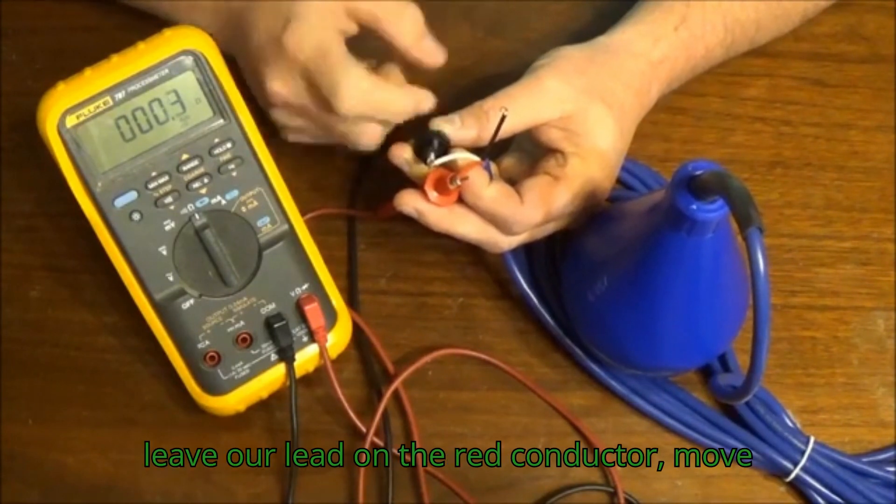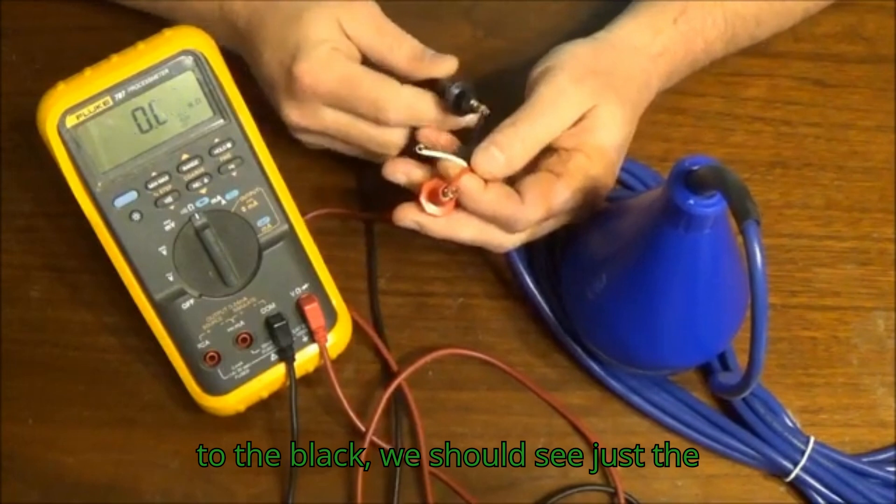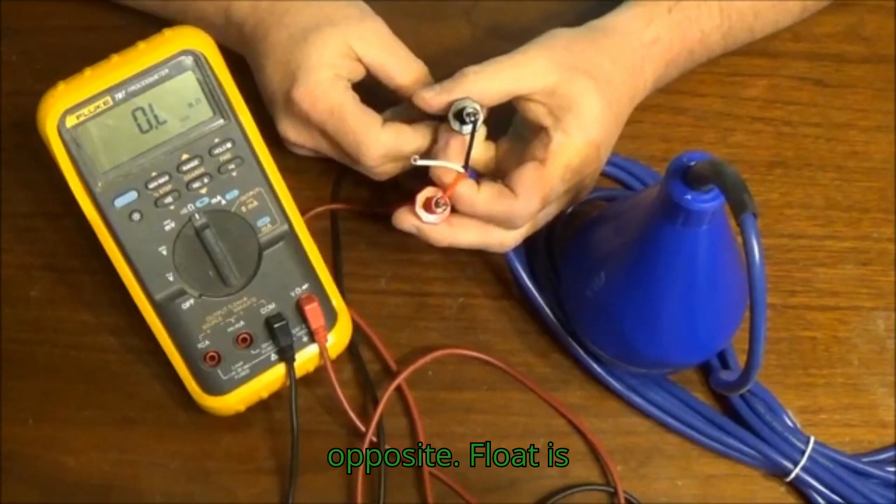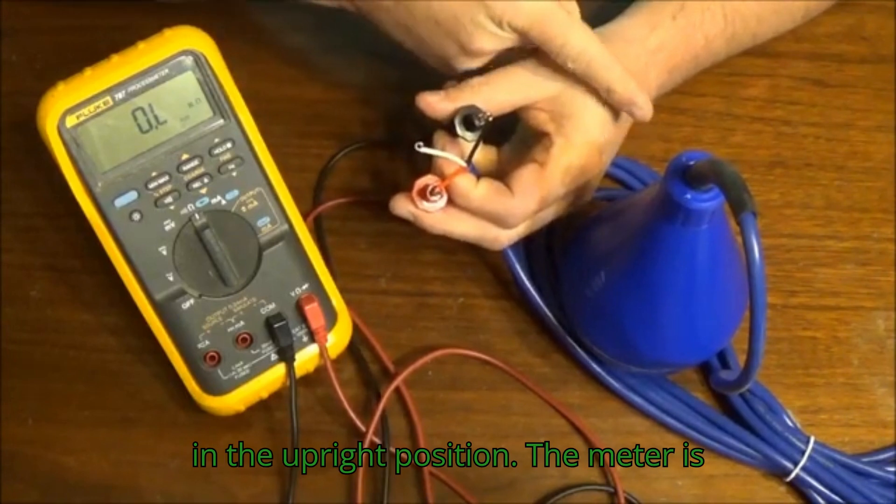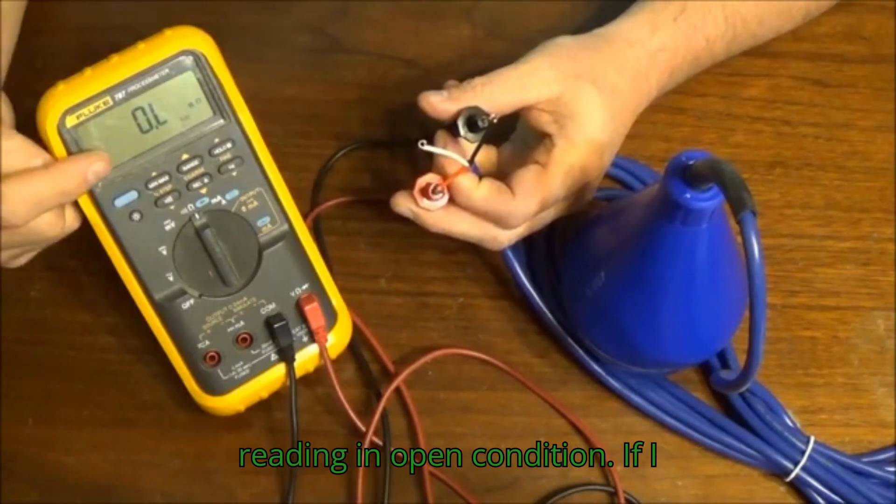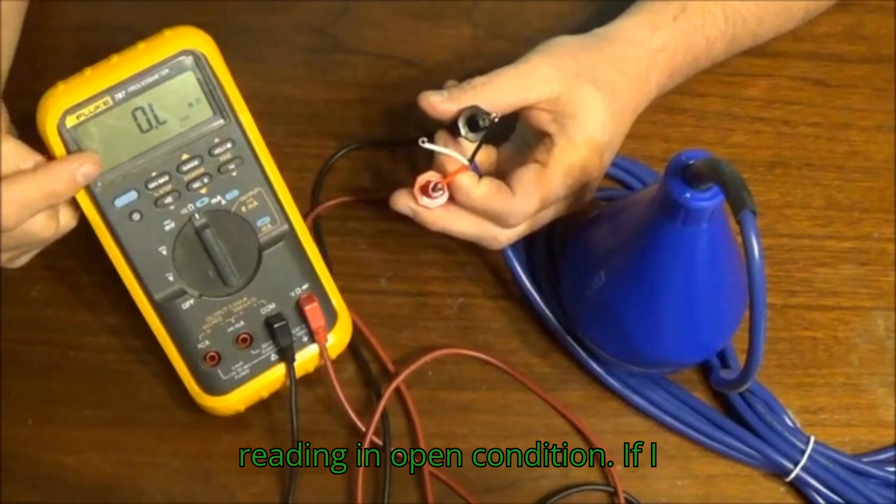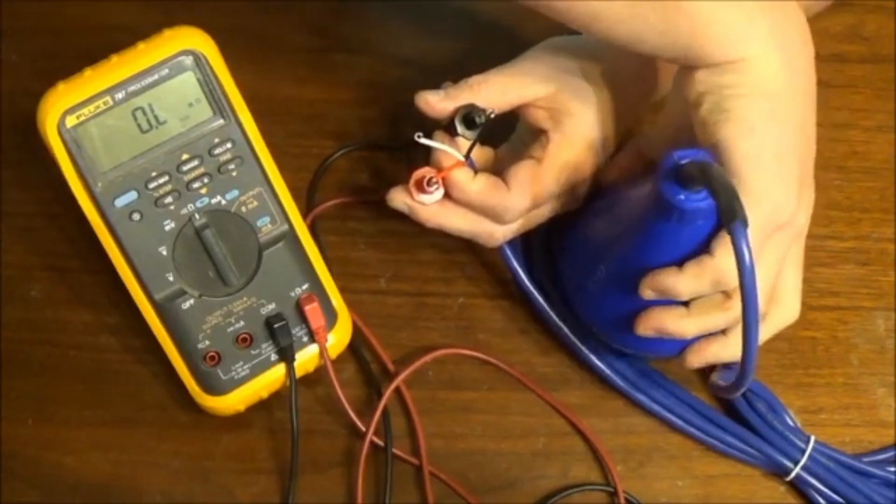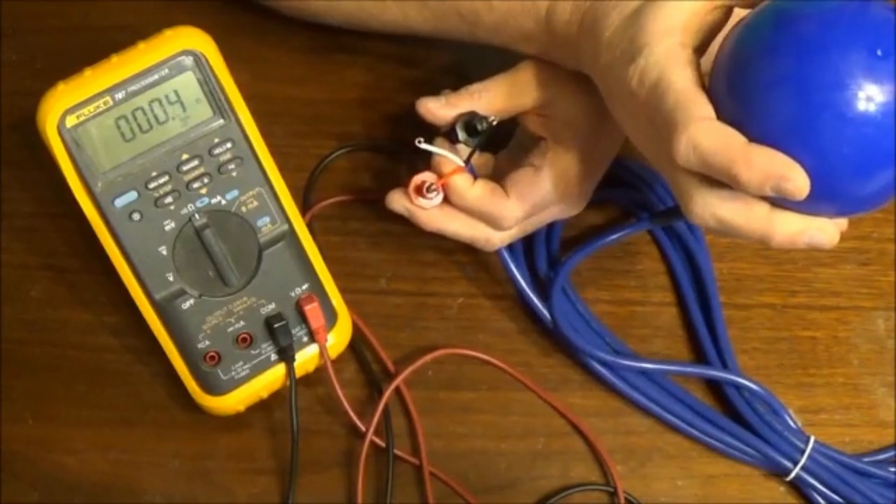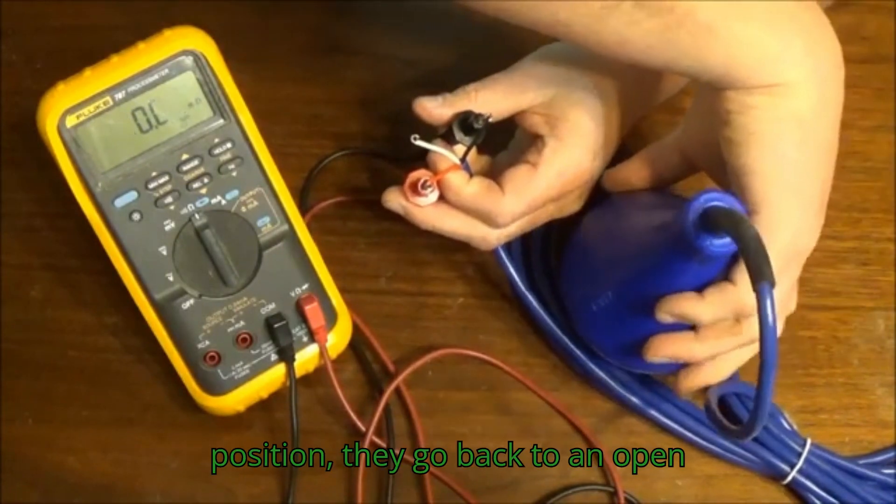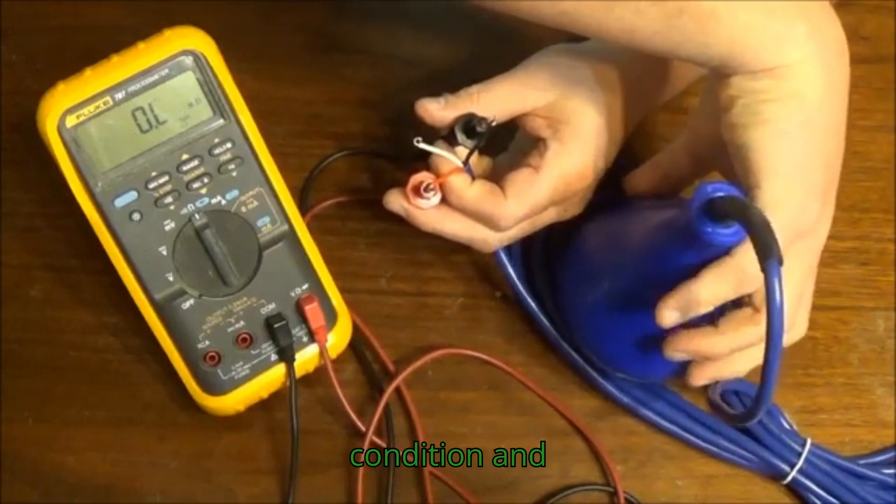Now if we leave our lead on the red conductor, move to the black, we should see just the opposite. The float is in the upright position, the meter is reading an open condition. If I toggle the float, we should see a shorted condition. Put the float back to its normal position, and go back to an open condition.